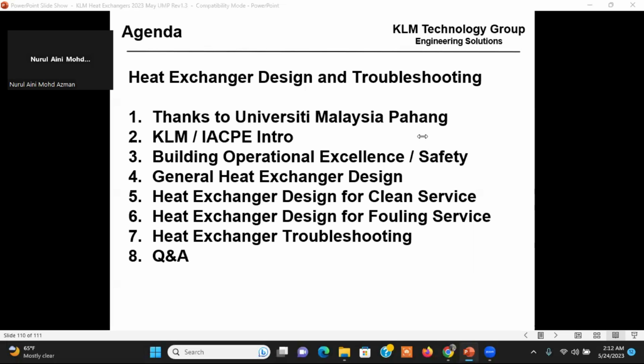All right. Next one. Hello, sir. How do you design simple heat exchangers for condensing design? A simple heat exchanger typically is liquid, and you don't have to worry about change of phase. Particularly if you have change of phase in water, or in a lot of hydrocarbons, that first drop of liquid can be very acidic. So you have to worry about corrosion and damage to the tubes wherever that first drop of liquid is made. So it's important. You might have to have better metallurgy. A lot of people will put a water wash, like in a crude column. You might put a water wash in front of that fin fan for that condenser design.